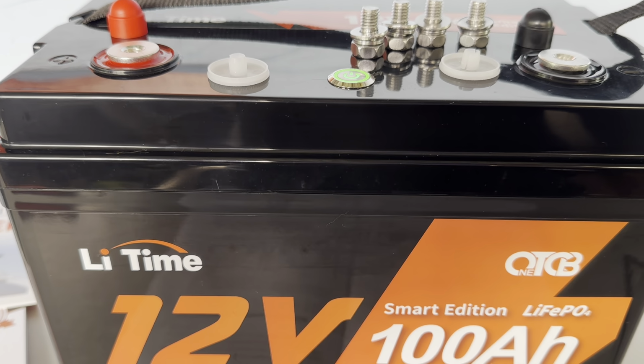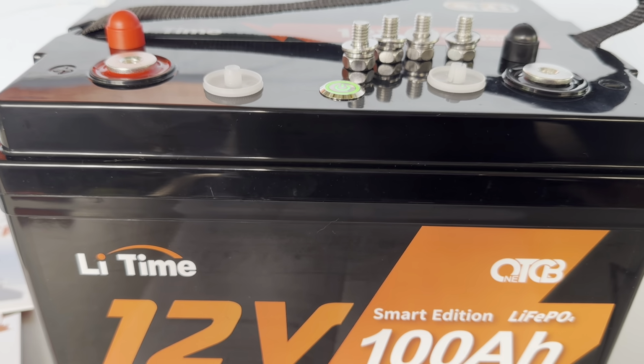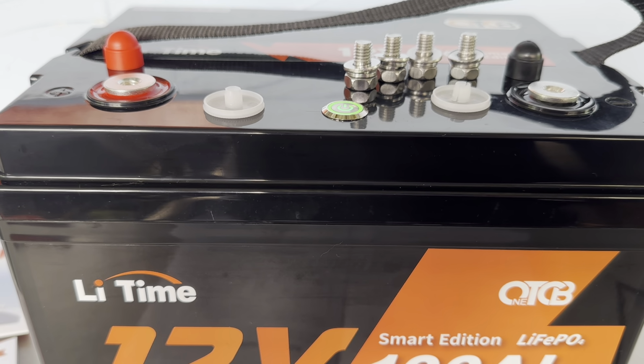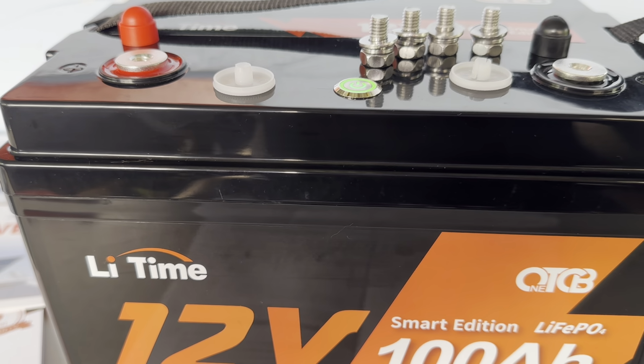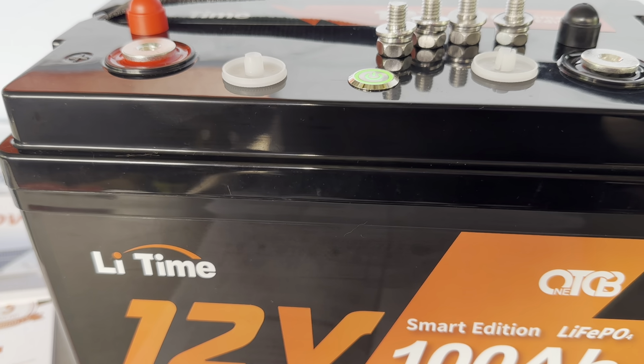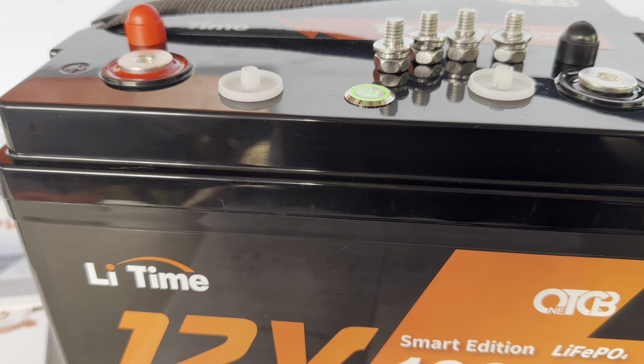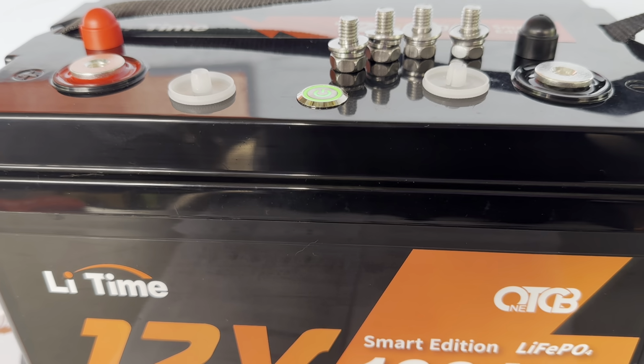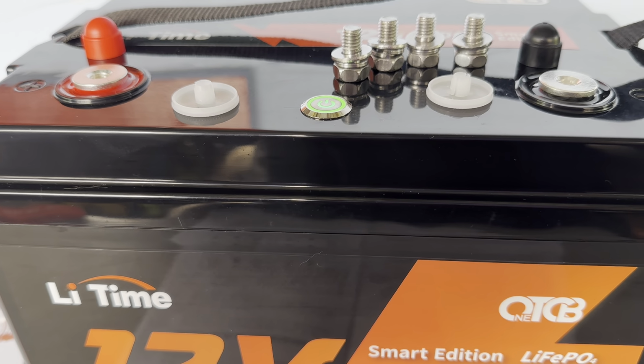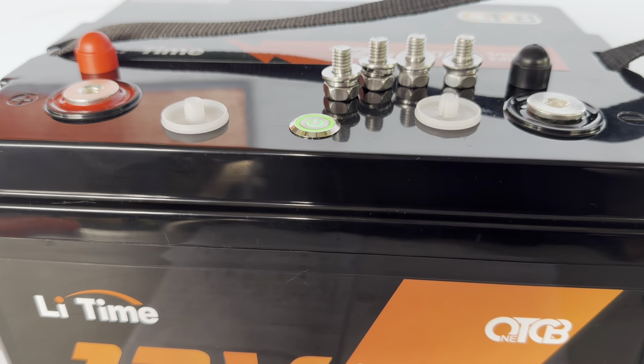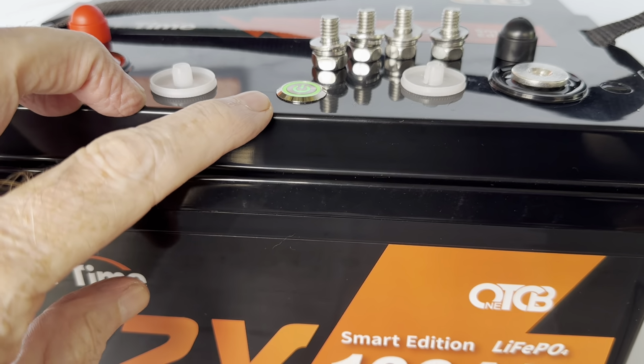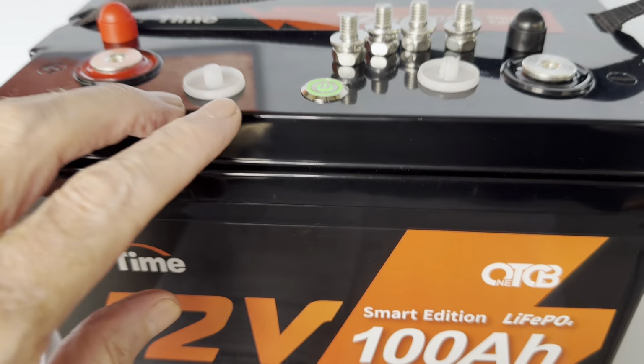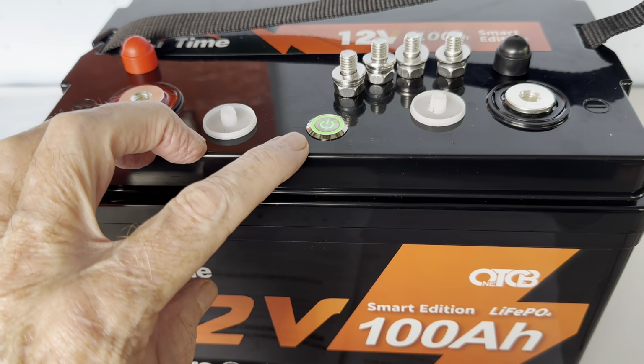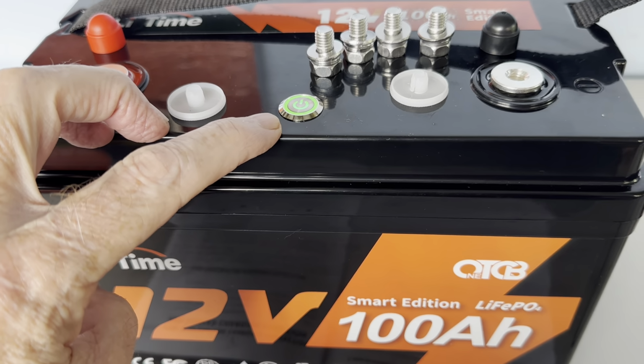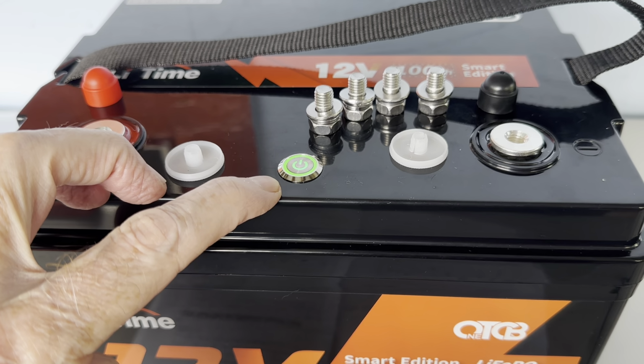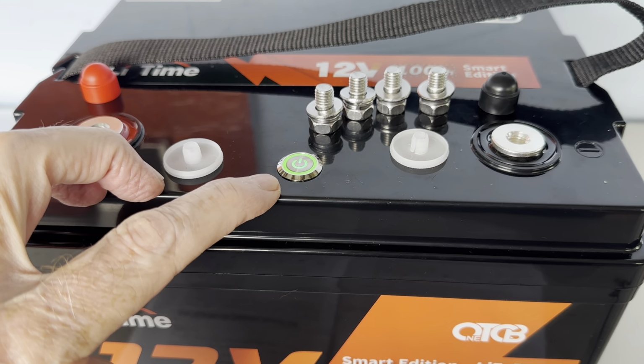This does have low temperature charging protection, so when the battery temperature is lower than 32 degrees Fahrenheit, the BMS will disconnect the battery to protect the battery. The LED indicator is a solid orange light when that has happened. So if you're down below 32 degrees, that BMS is going to kick on to protect it. And what there is on this, which is kind of neat, it won't really apply for people in warmer climates, but if you're in a colder climate, you can override that low temperature charging protection for an emergency type of use.